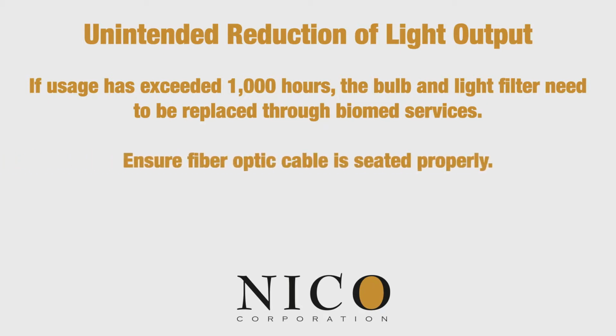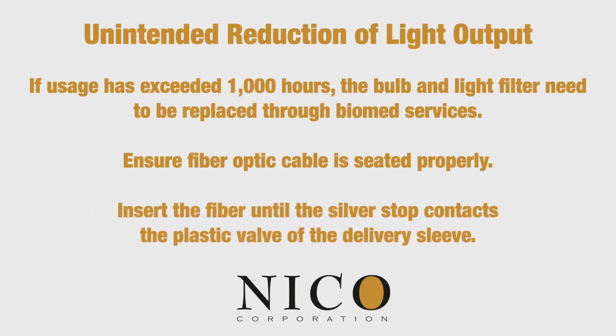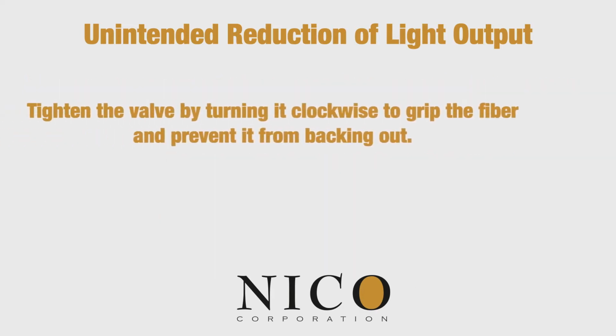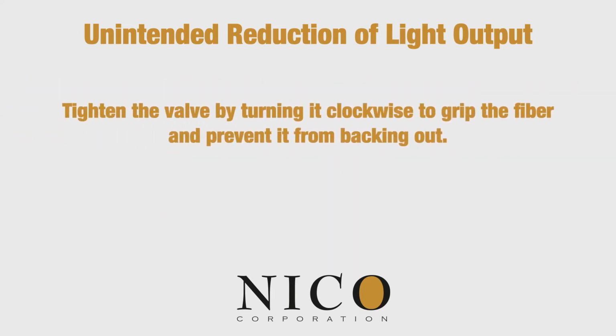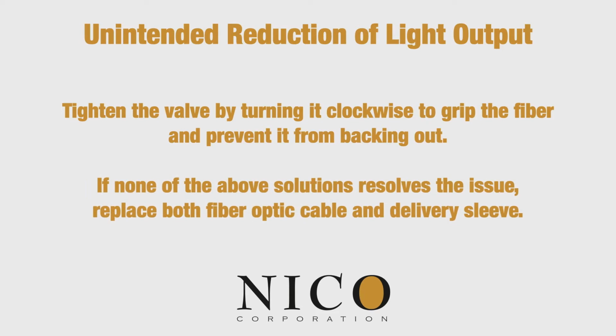Ensure the fiber optic cable is seated properly. Insert the fiber until the silver stop contacts the plastic valve of the delivery sleeve. Tighten the valve by turning it clockwise to grip the fiber and prevent it from backing out. If none of the above solutions resolves the issue, replace both fiber optic cable and delivery sleeve.